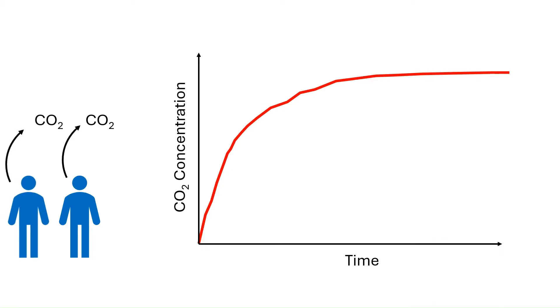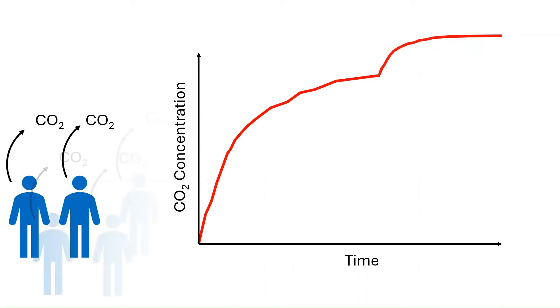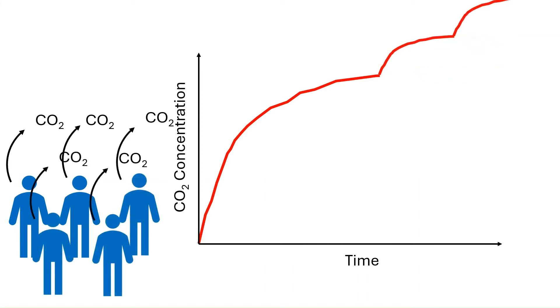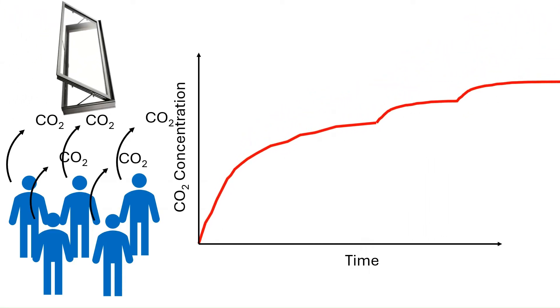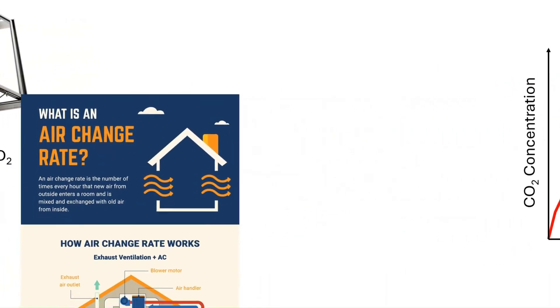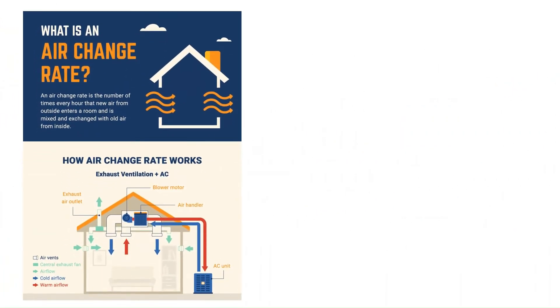If a second person enters the room, the CO2 concentration will increase again, reaching a new, higher steady state. This trend continues as more and more people enter the room. If the ventilation rate is changed, a new steady state will be reached. The ventilation rate is reported as air changes per hour — ACH for short. The higher the ACH, the lower the maximum CO2 and thus the lower the amount of infectious aerosol in the room.